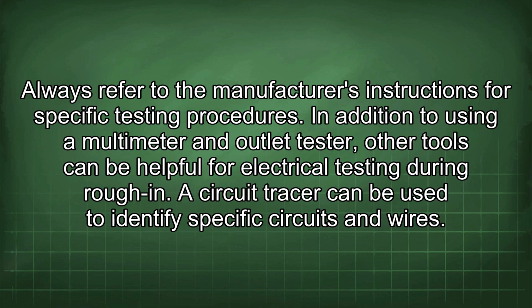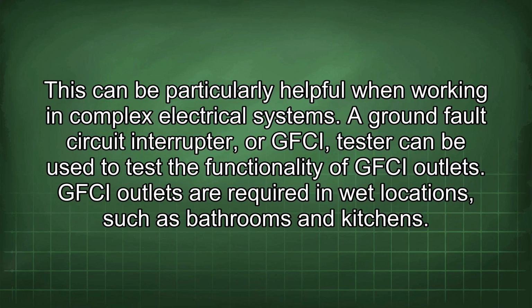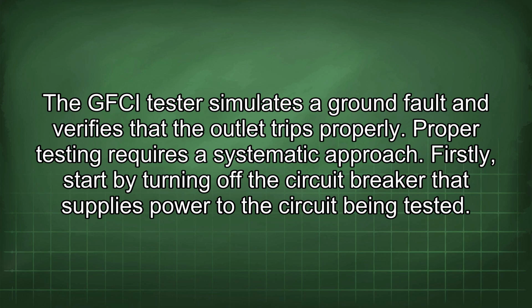In addition to using a multimeter and outlet tester, other tools can be helpful for electrical testing during rough-in. A circuit tracer can be used to identify specific circuits and wires. This can be particularly helpful when working in complex electrical systems. A ground fault circuit interrupter, or GFCI tester, can be used to test the functionality of GFCI outlets. GFCI outlets are required in wet locations, such as bathrooms and kitchens. The GFCI tester simulates a ground fault and verifies that the outlet trips properly. Proper testing requires a systematic approach.